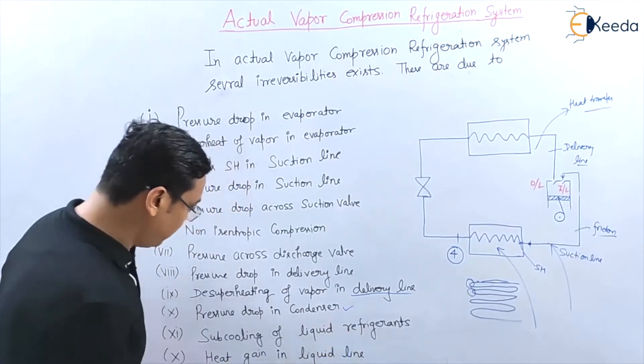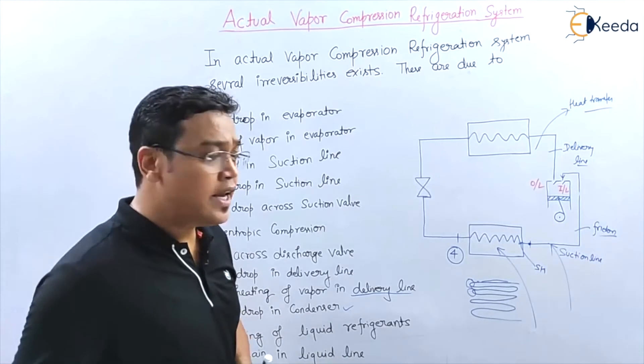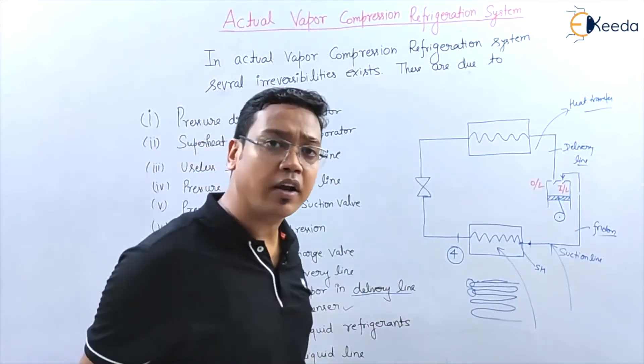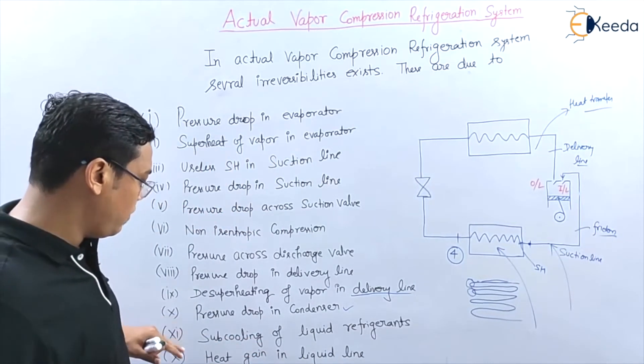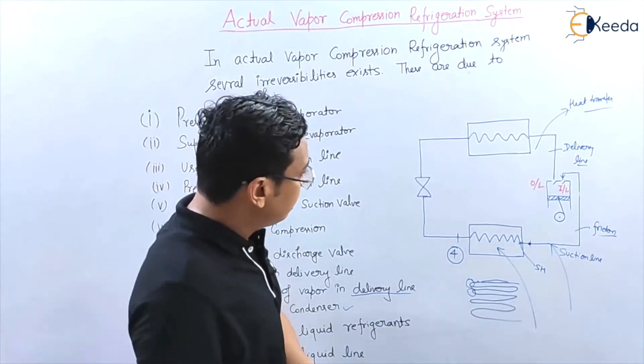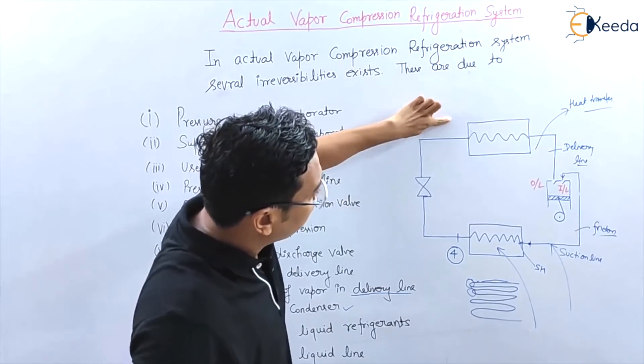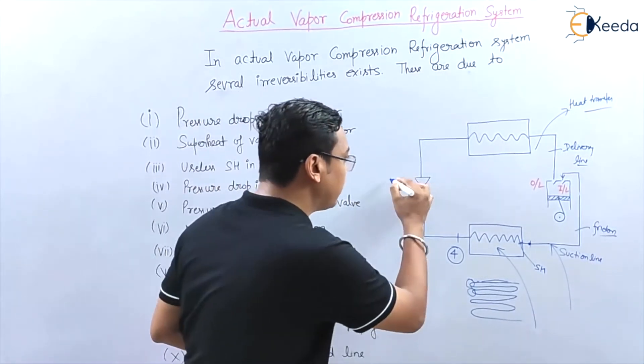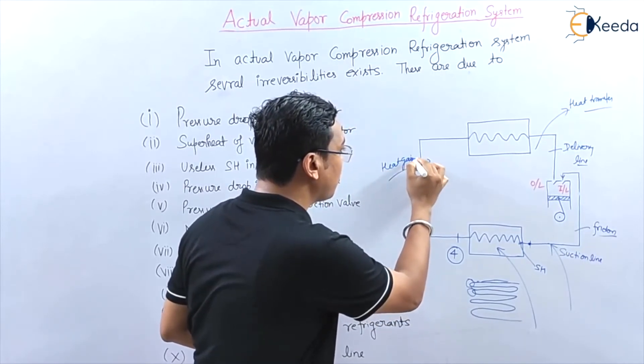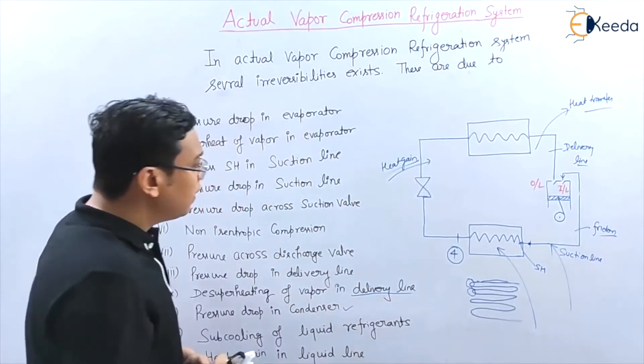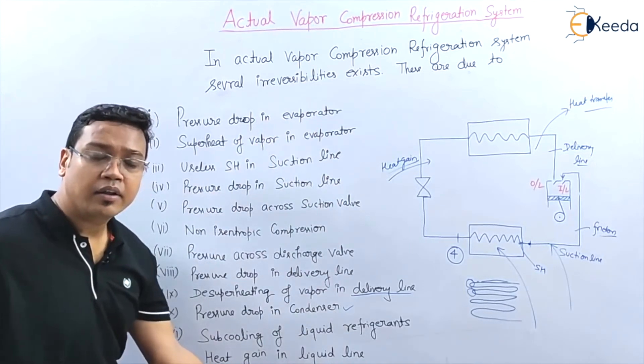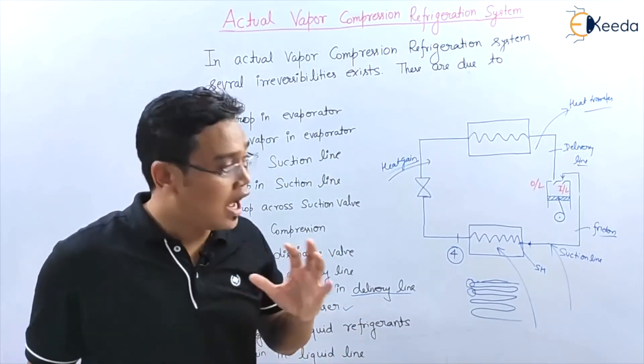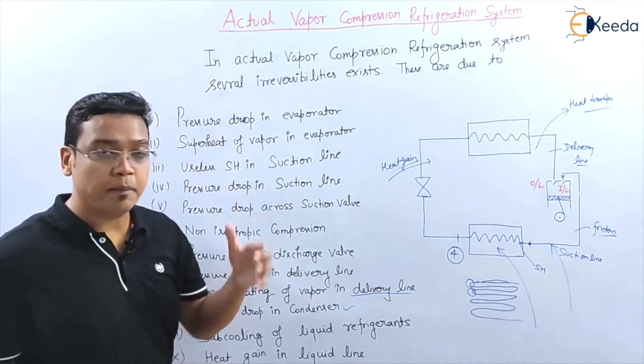The next point is subcooling of the liquid refrigerant. In the condenser, extra heat is given to the surrounding, so subcooling of the liquid refrigerant occurs within the condenser itself. Additionally, there is heat gain in the liquid line before the expansion valve, where the refrigerant absorbs heat. All these irreversibilities make the actual vapor compression refrigeration system different from the ideal one.